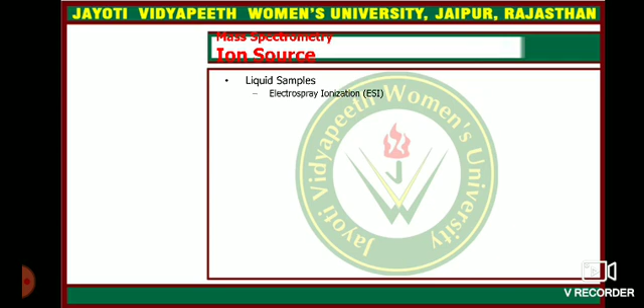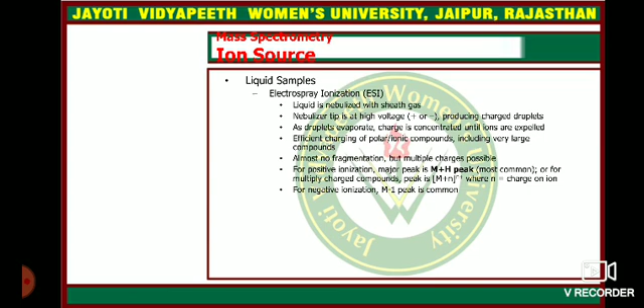For liquid samples, as in electrospray ionization, the liquid is nebulized with sheath gas. The nebulizer tip is at high voltage, and as droplets evaporate, charge is concentrated until ions are expelled. It efficiently charges polar compounds, including very large compounds, with almost no fragmentation, but multiply charged ions are possible. For positive ionization, the major peak is the M plus H peak. For negative ionization, the M minus 1 peak is common.